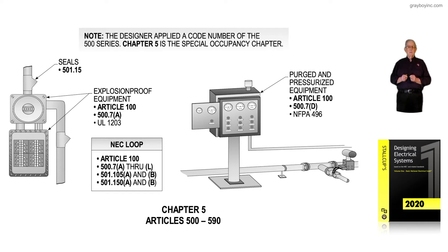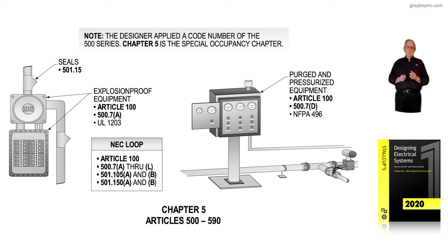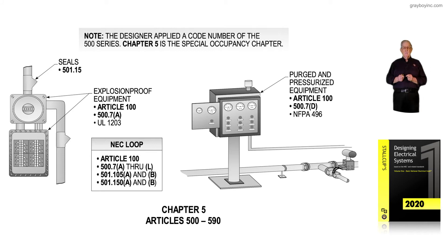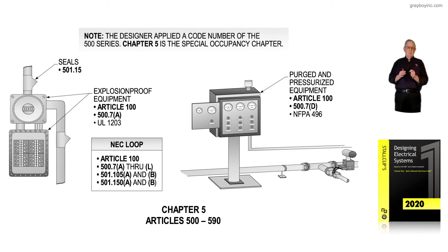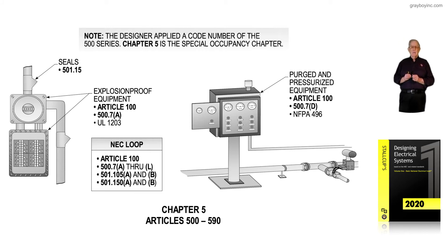The NEC notes that 500.2 will no longer contain definitions — it's Article 100 Part 3 now. The definitions were moved and scattered through Article 100, and designers in hazardous locations, as well as electricians and inspectors, really didn't like that. They said the definitions were harder to find. So they provided a Part 3 and put all the definitions there in alphabetical order, making them easier to find, like they used to be in 500.2. So 500.7A through L deals with the protection techniques allowed in classified locations.